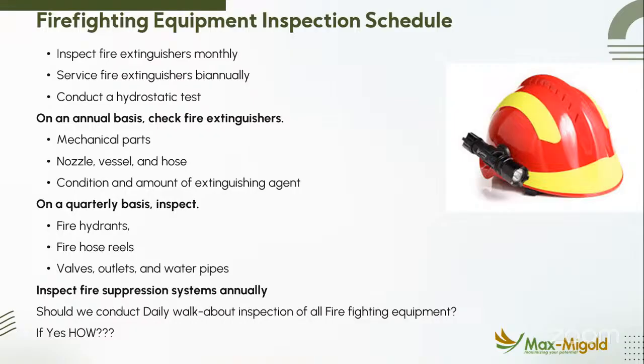So on that monthly basis, if you have a fire pump, it should be done even on a weekly basis, because there is the battery part for the electrical pump in the firehouse. So if you have a hydrant system or a sprinkler system with a fire pump, please, as a routine, every Friday, the fire pumps should be inspected, whether it's the jockey, electric or diesel pump. That should be weekly. On a quarterly basis, ensure that you do a deep inspection of the hoses, hydrants, valves, and outlets, to ensure that they are not stiff and they are good to go.